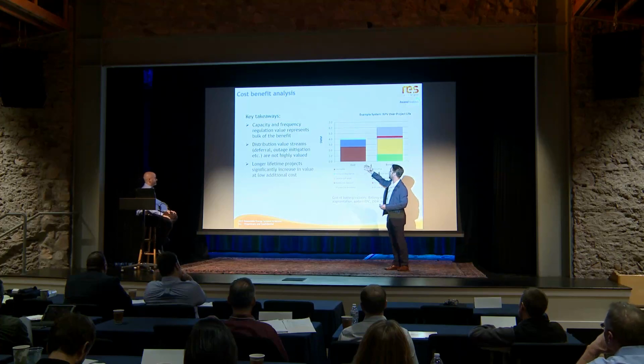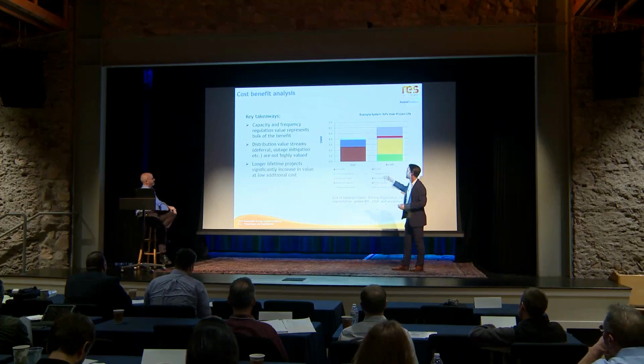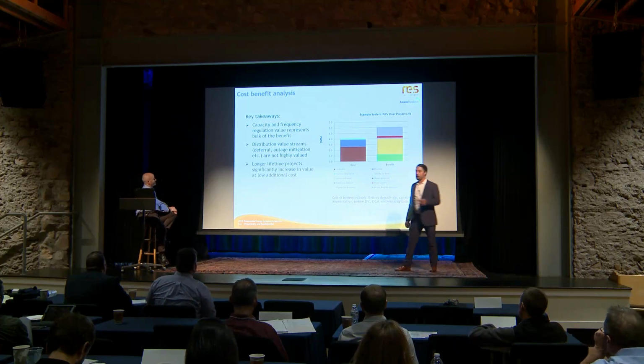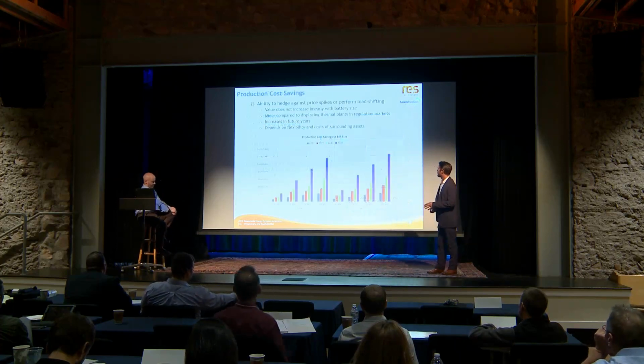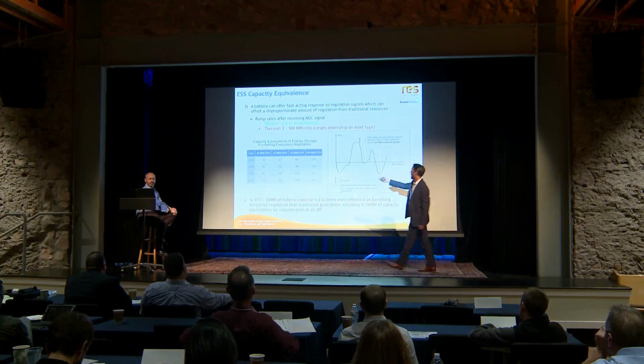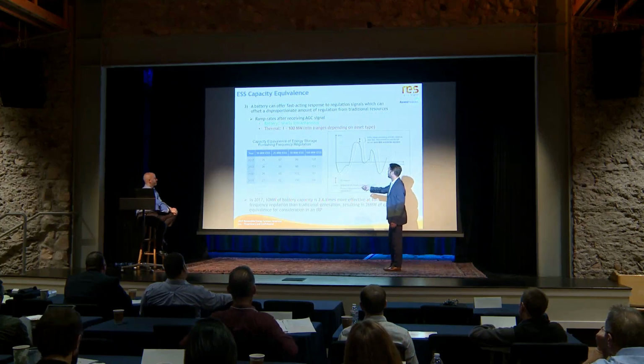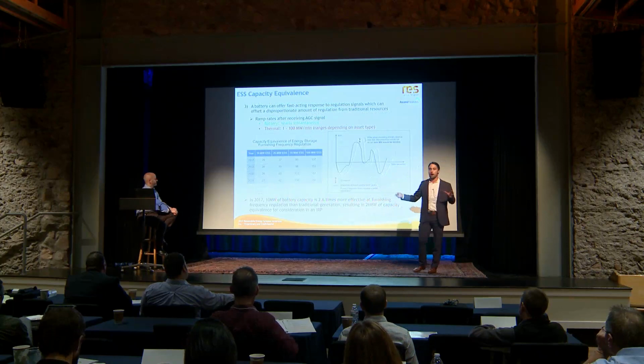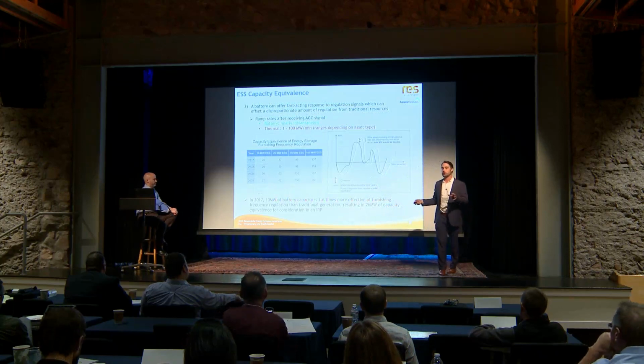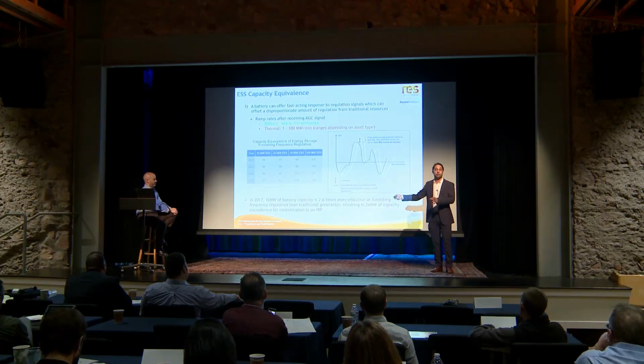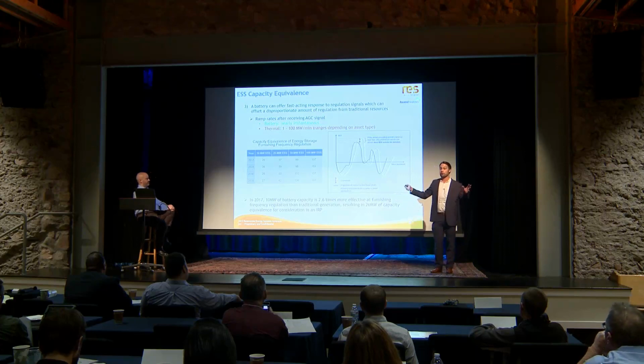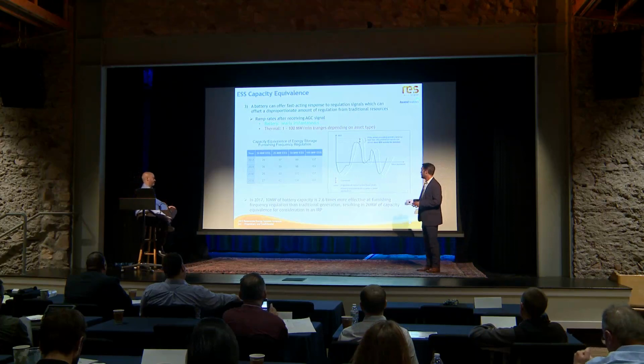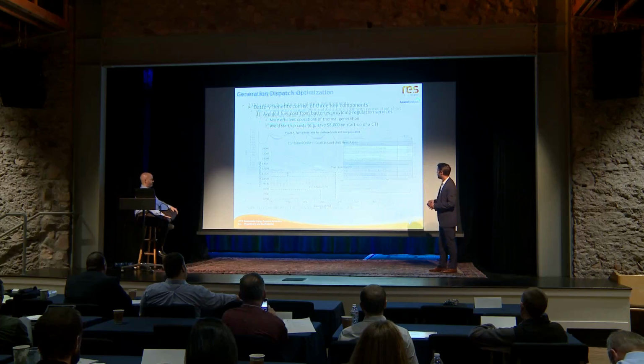So some of the key takeaways are that capacity and frequency regulation value represents the bulk of the benefit. If you're not clear on how we're getting capacity value, remember this graph—this is a capacity equivalence. This 10 megawatt storage asset is basically freeing up 26 megawatts of thermal generation to go do something else other than frequency regulation, typically a longer duration service, especially if it's a coal plant. So that's actually capacity value that was created, and we're able to capture that.